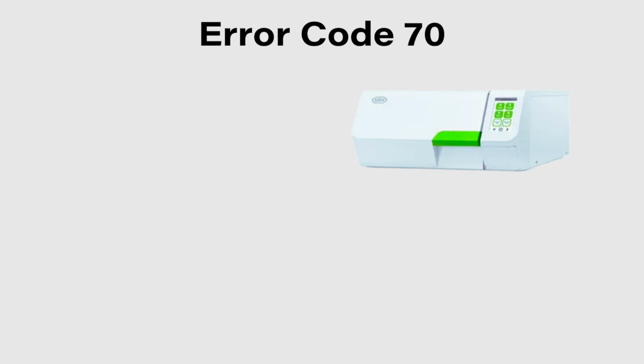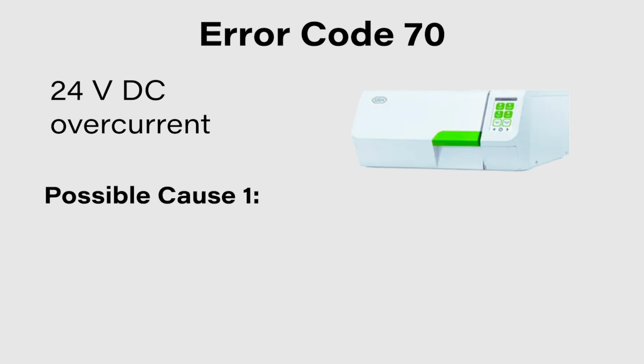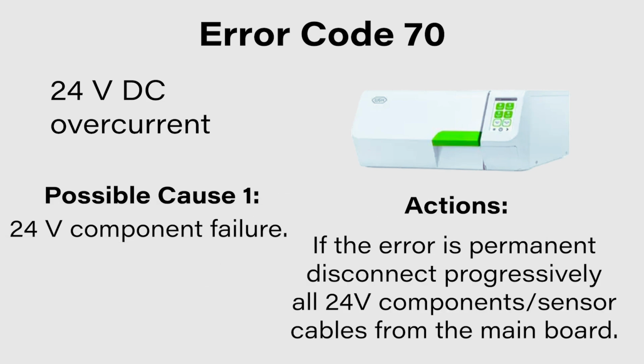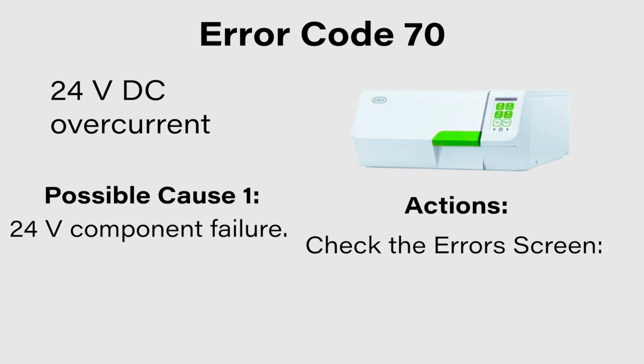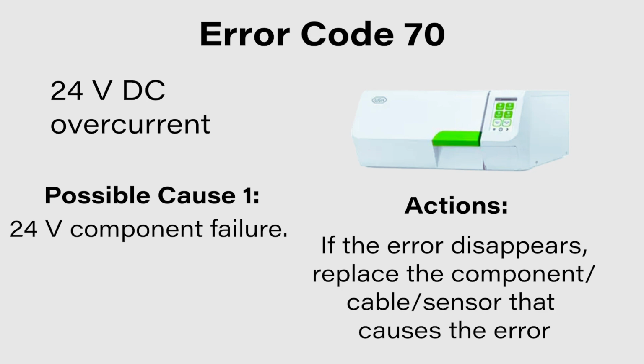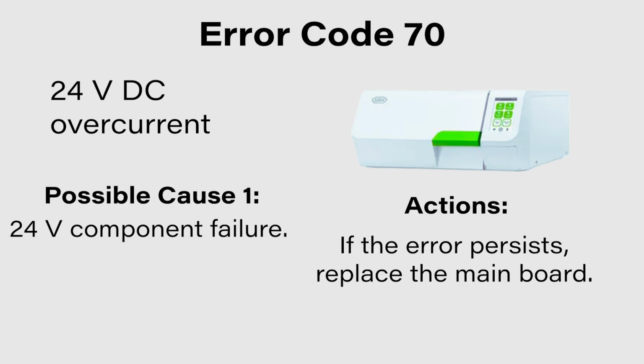If your W&H Lexa Mini Autoclave is displaying an error code 70, that means that there was a 24-volt DC overcurrent. The first possible cause could be a 24-volt component failure. For this, if the error is permanent, disconnect progressively all 24-volt components/sensor cables from the main board. Check the error screen. If the error disappears, replace the component, cable, or sensor that causes the error. If the error persists, replace the main board.